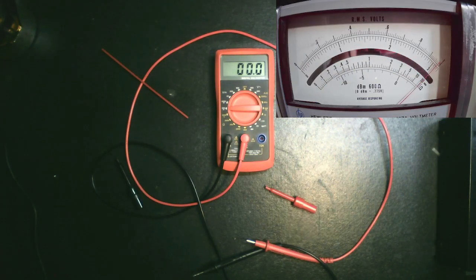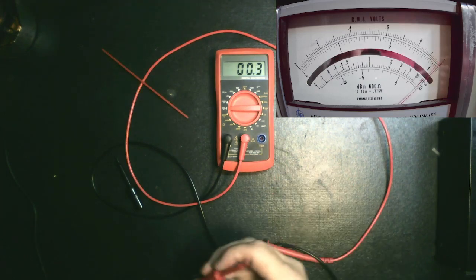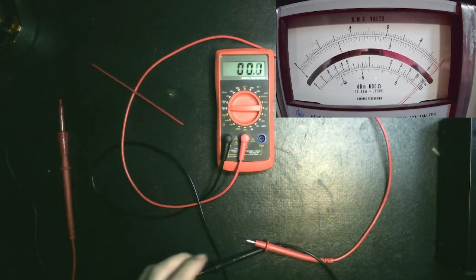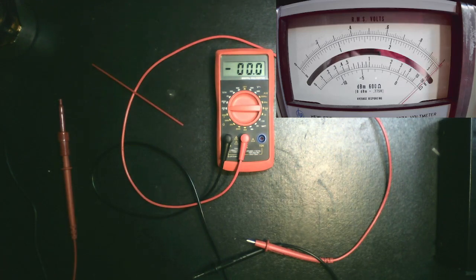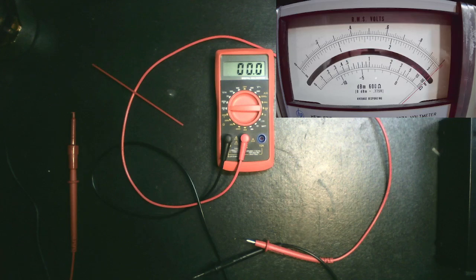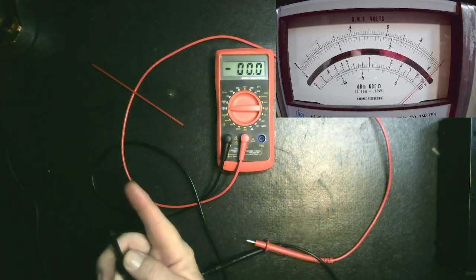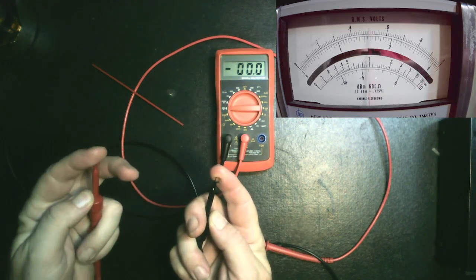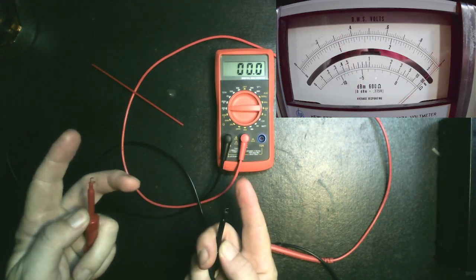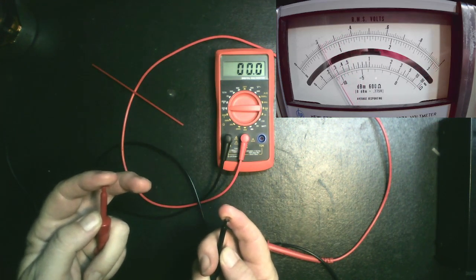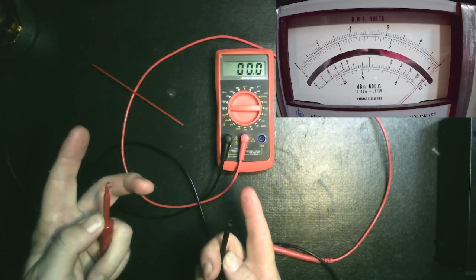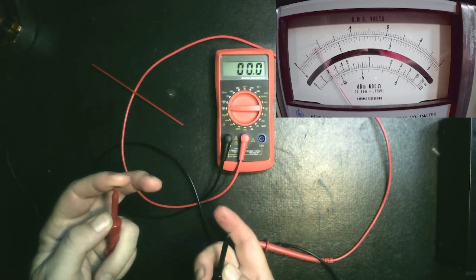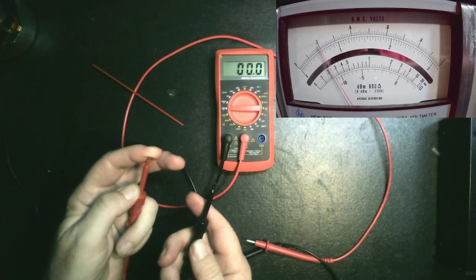Got too many test leads out here. I'm going to go ahead and put these on here. We're dealing with such high resistances here that I don't want my body to be part of the reading. Just to give you an example, these are the two test leads going to that. If you look at the meter there, just me touching it, see how much of a drop it makes on that 10 mega ohm range? I mean, even if I'm just touching one of them.